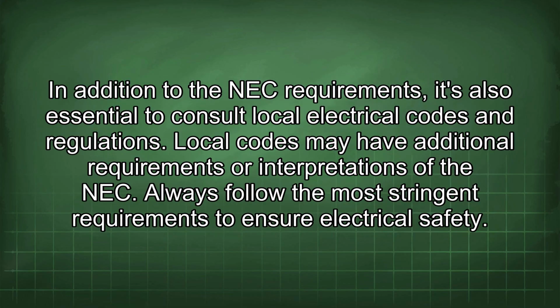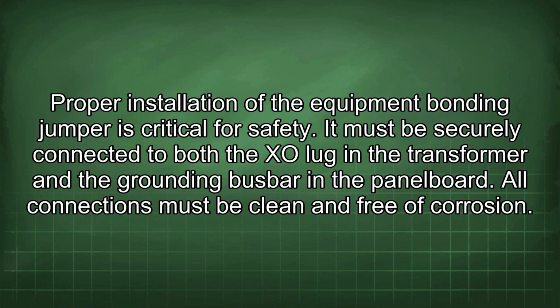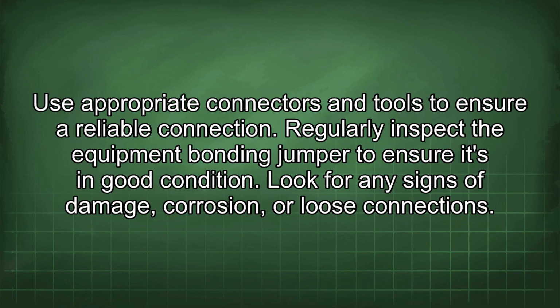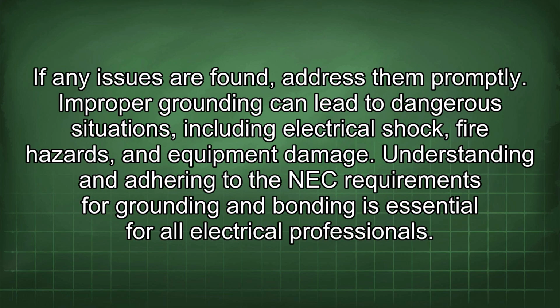In addition to the NEC requirements, it's also essential to consult local electrical codes and regulations. Local codes may have additional requirements or interpretations of the NEC. Always follow the most stringent requirements to ensure electrical safety. Proper installation of the equipment bonding jumper is critical for safety. It must be securely connected to both the XO lug in the transformer and the grounding busbar in the panel board. All connections must be clean and free of corrosion. Use appropriate connectors and tools to ensure a reliable connection. Regularly inspect the equipment bonding jumper to ensure it's in good condition. Look for any signs of damage, corrosion, or loose connections. If any issues are found, address them promptly.